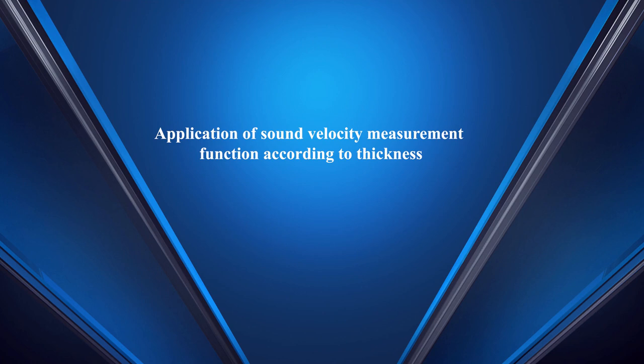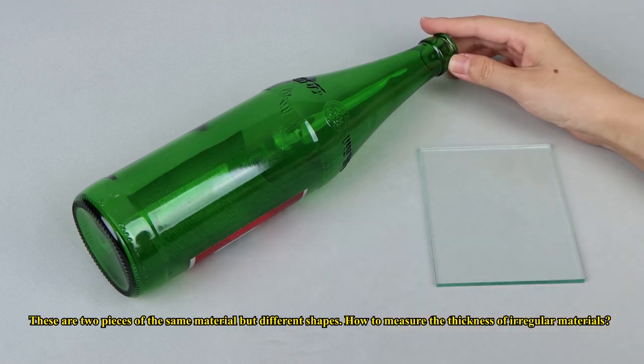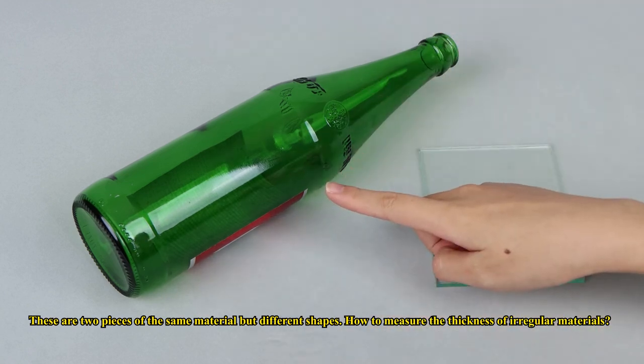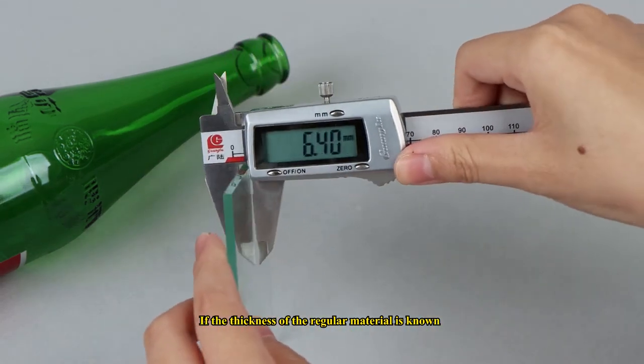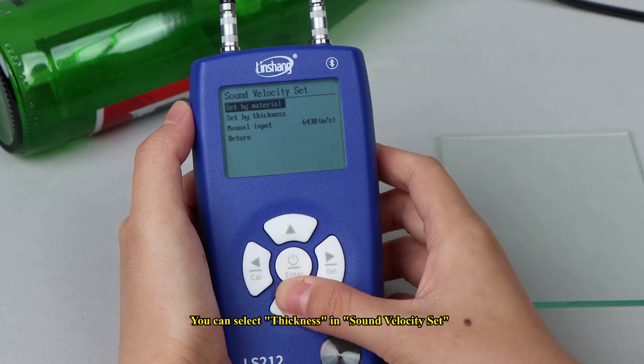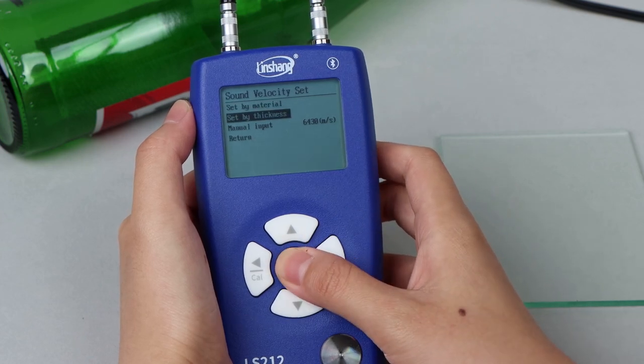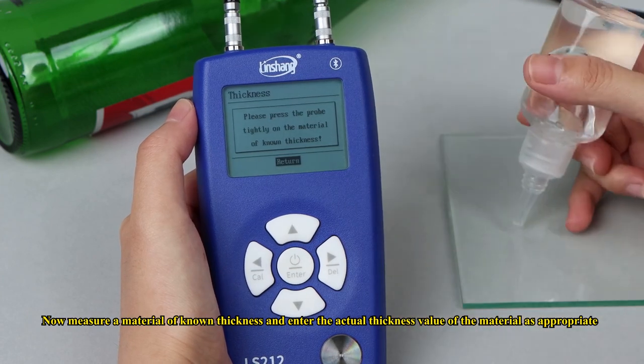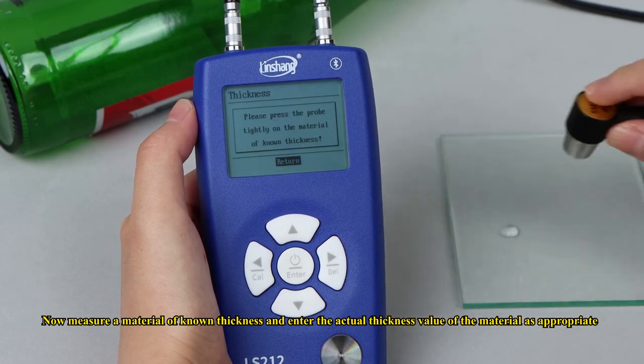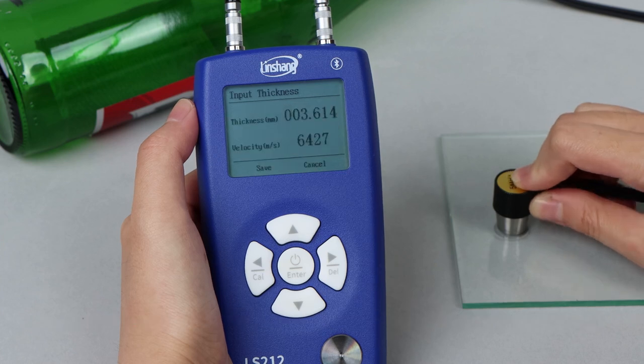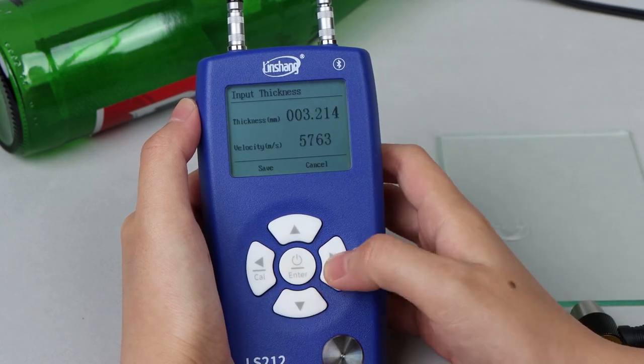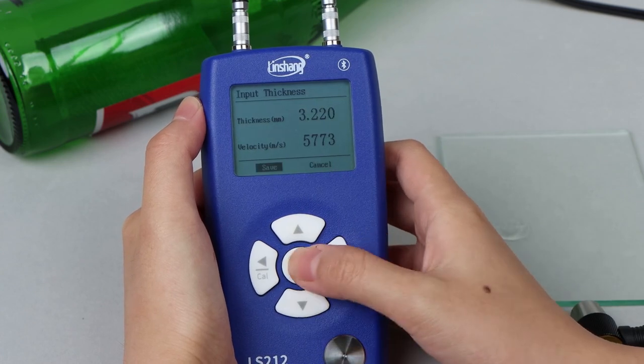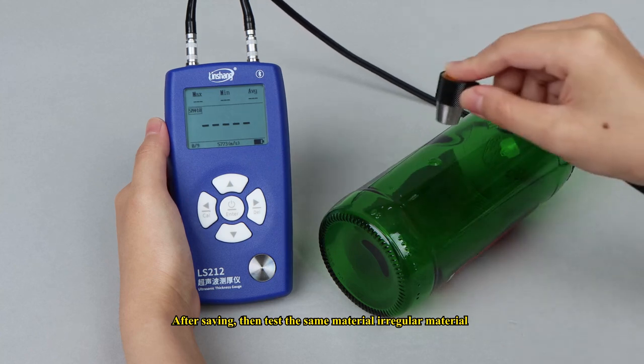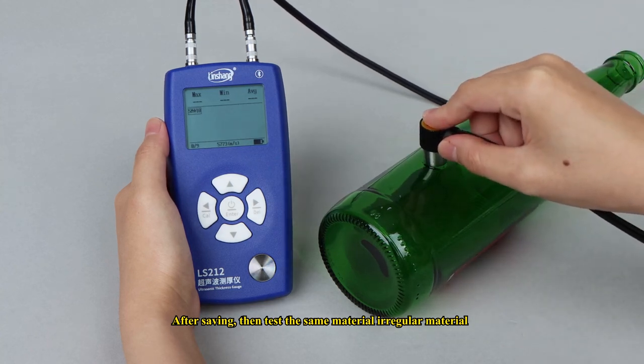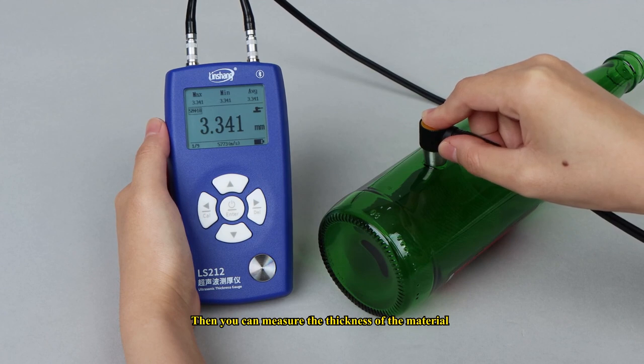Application of the sound velocity measurement function according to thickness. These are 2 pieces of the same material but different shapes. How to measure the thickness of irregular materials. If the thickness of the regular material is known, you can select thickness in sound velocity set. Now measure a material of known thickness and enter the actual thickness value of the material as appropriate. After saving, then test the same irregular material. Then you can measure the thickness of the material.